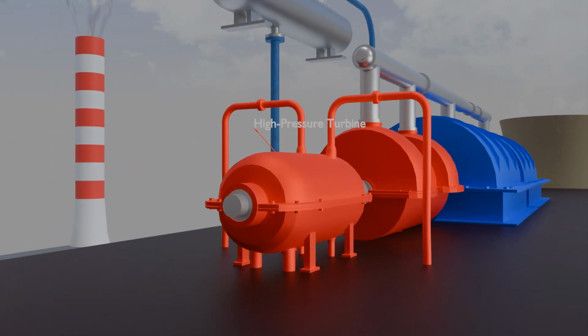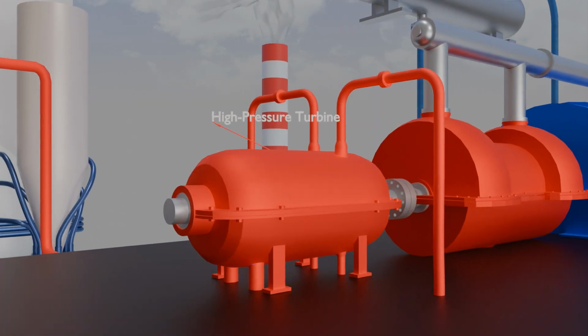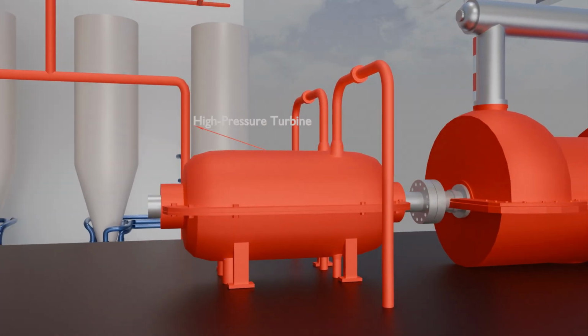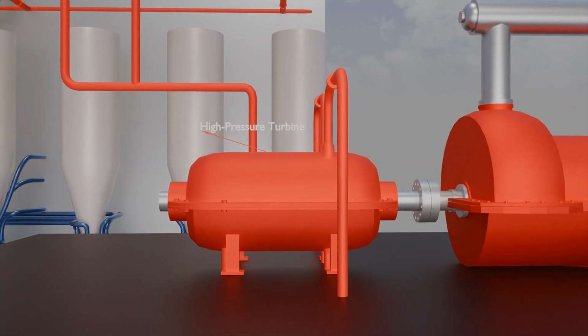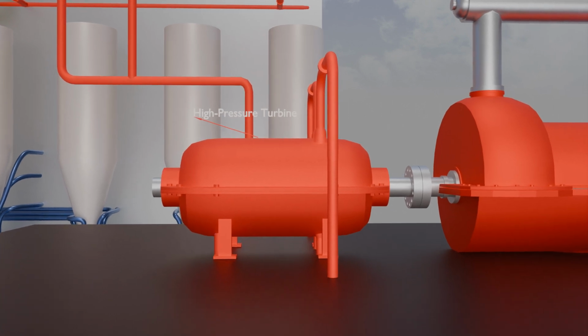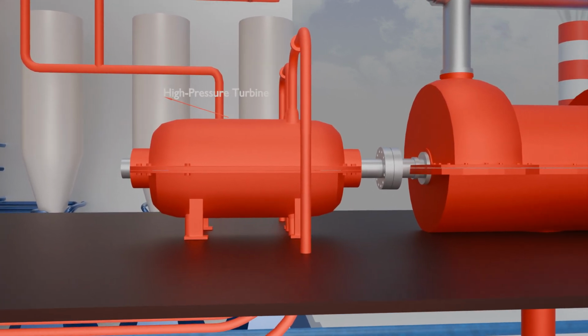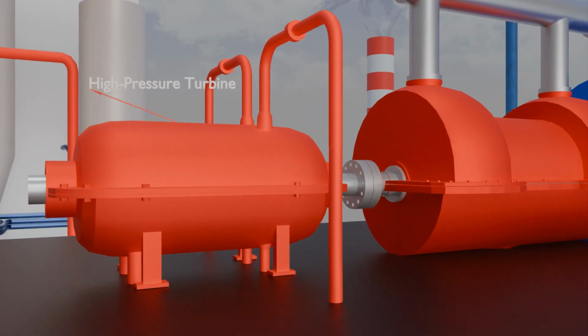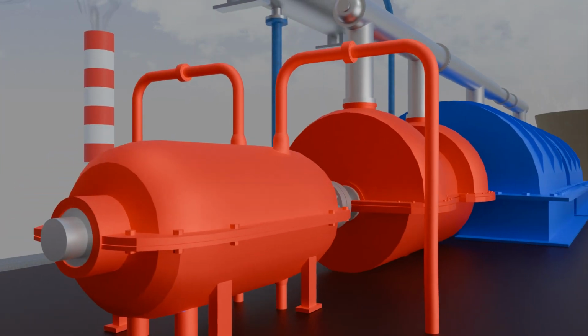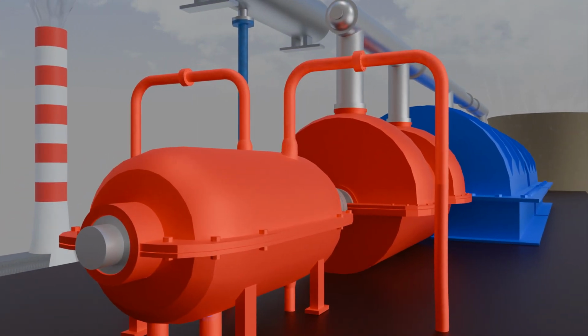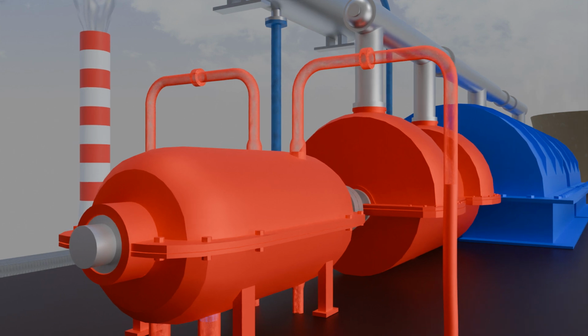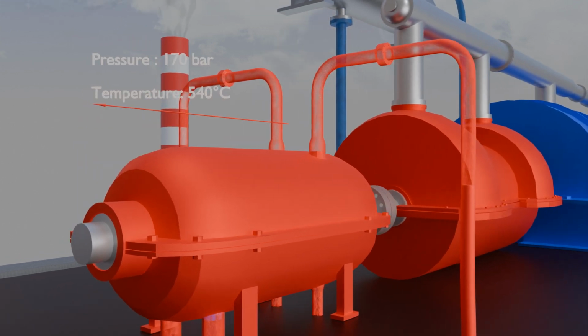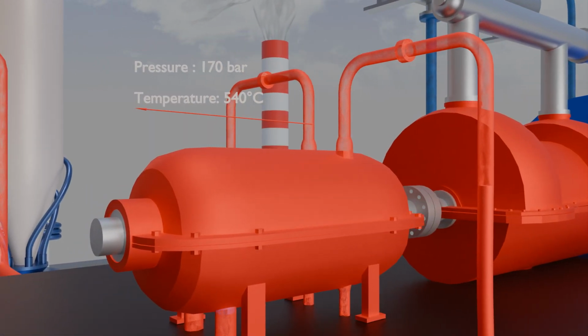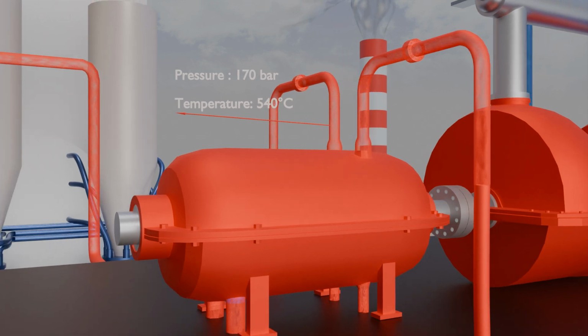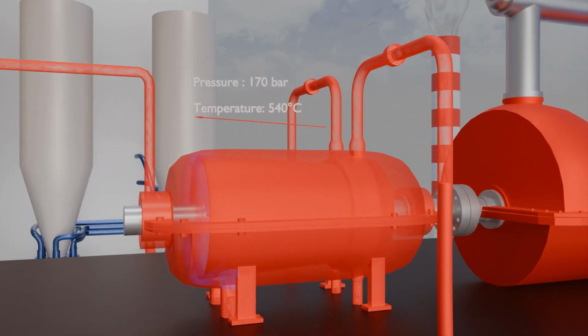This is the high-pressure turbine, a critical component in the power generation process. Steam from the boiler enters this turbine at an incredibly high pressure and temperature, ready to begin the process of energy conversion. The steam enters through this inlet, carrying immense kinetic and thermal energy. At this point, the pressure is around 170 bar, and the temperature can reach up to 540 degrees Celsius.